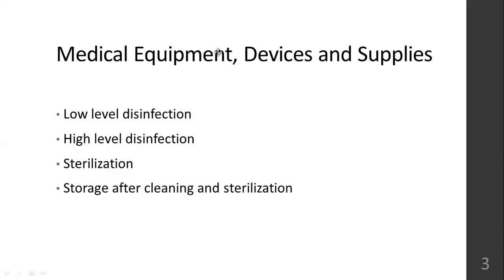So what are the agents used in high-level disinfection? 2% glutaraldehyde solution, 7.5% hydrogen peroxide, peracetic acid, ortho-phthalaldehyde, and the contact time is also kept for at least 20 to 30 minutes. The items should be in contact with the disinfectant. Only then will it work properly. So these are the three main levels of disinfection.